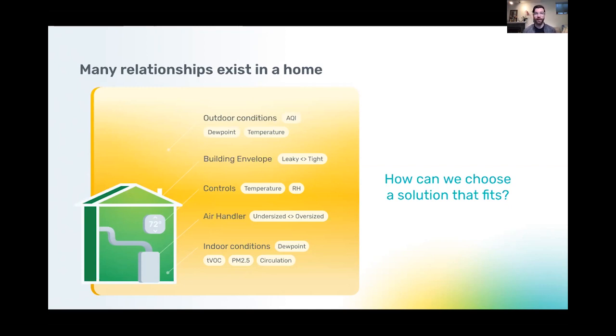And so HVAC runtime is incredibly important to all three pillars, and it doesn't happen often unless you have a properly sized piece of equipment in the right climate zone, with the exception being something like a dedicated ERV system, meaning it has its own ductwork, it's running on its own without the HVAC system being tied to it, without being interlocked to it.